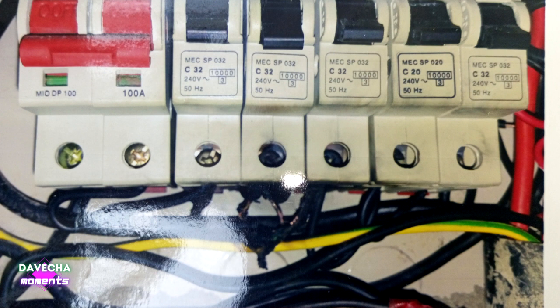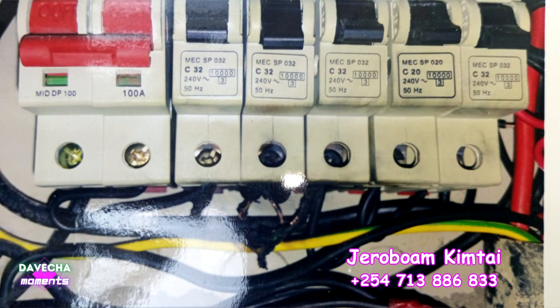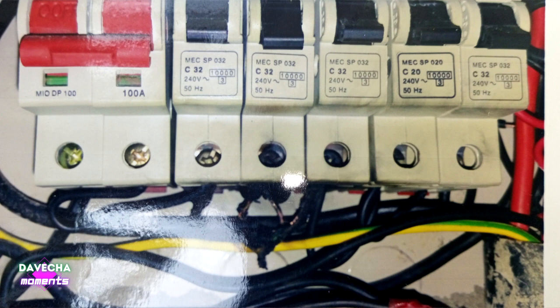So this fourth circuit breaker from the right is the one that caused this problem of the soot you can see. There was a fire occurring just because the terminal at the circuit breaker at the bottom was not tight enough to avoid arcing, and then avoid oxidation and resistance that will also cause a heating effect on the wire and eventually peel off the insulation. In this particular wire, again, as you can see, it is broken. It is cut because of the heat. This eventually caused the whole house to be in blackout because the wire was then not looped to the next circuit breakers going to the right. And that is the effect of loose connection.